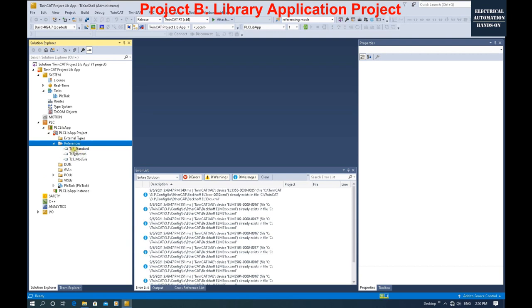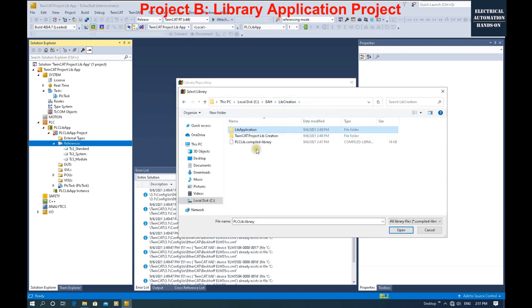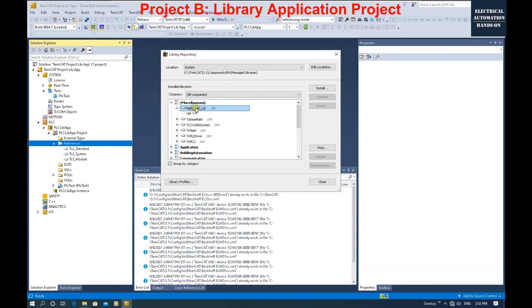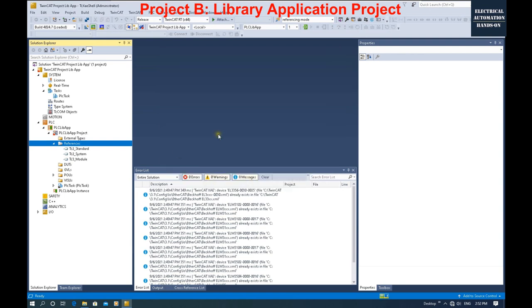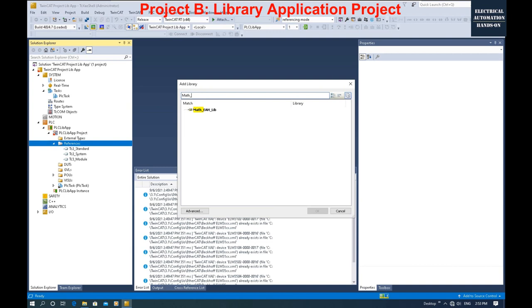Here the TC2 and TC3 libraries all come from TwinCAT's built-in libraries. Now we need to install the library we just exported from another project. Click 'Library Repository' and then click 'Install.' Go to the directory where we exported the file — the sealed compiled library. Click Open. After we install this library it will show here — we imported the library named 'math_underscore_EAH_underscore_library.' Now click Close, then go to 'Add a Library.' We can search the library we just installed, named 'math_underscore_EAH_underscore_library,' and click OK.